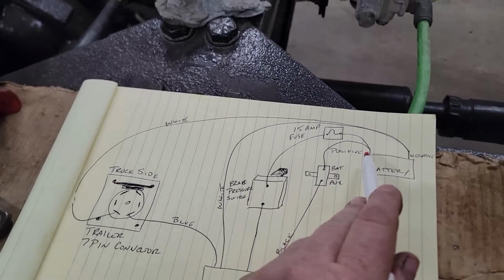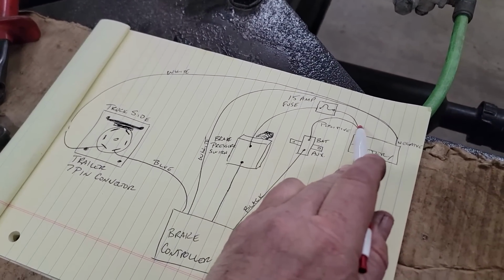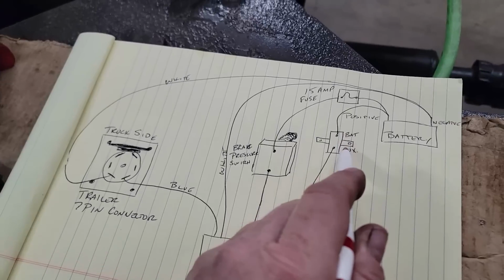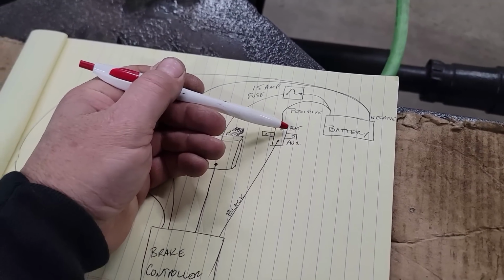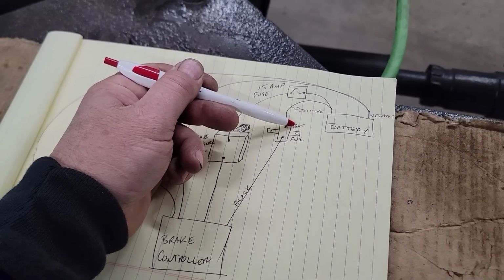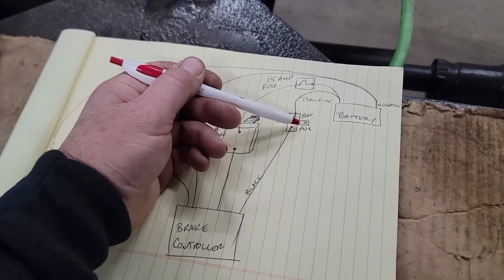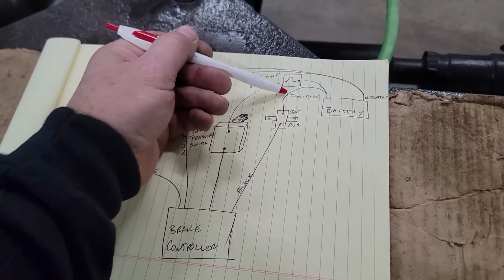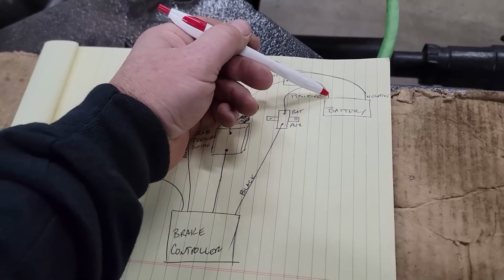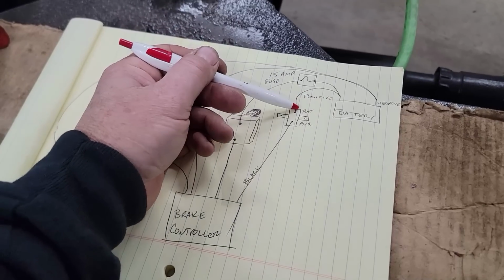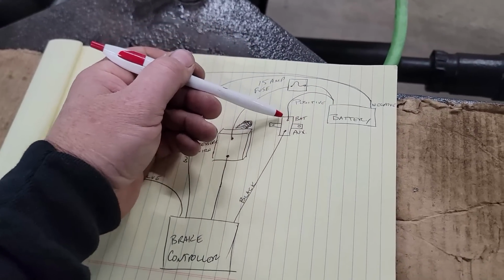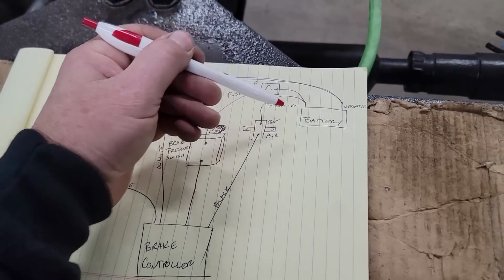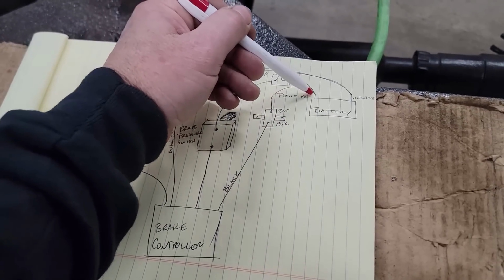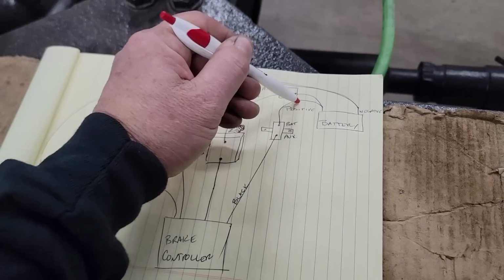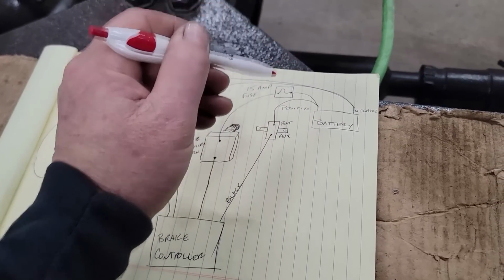Then we're going to take a positive line off the battery, coming real close to the battery and hitting our circuit breaker. Our circuit breaker has 2 terminals, and it's important to pay attention to them. One is battery side, the other is auxiliary. The auxiliary is the load; the battery side is the supply closest to the battery. It's important that this distance be as short as feasible, because before this there's no overcurrent protection. If it shorts out, gets cut or pinched, there's nothing to stop it from burning up. So we want that connection as close to the battery as possible.